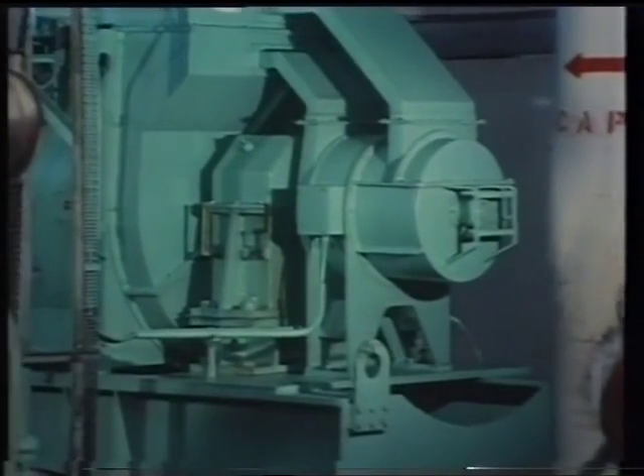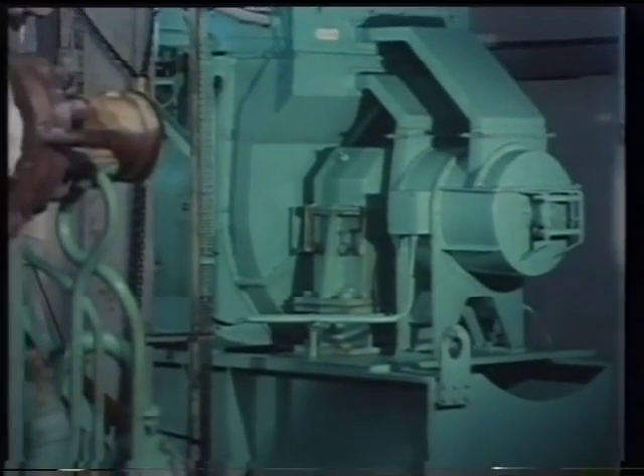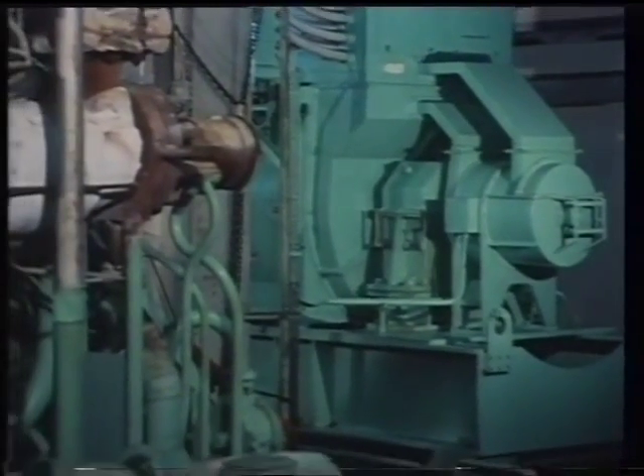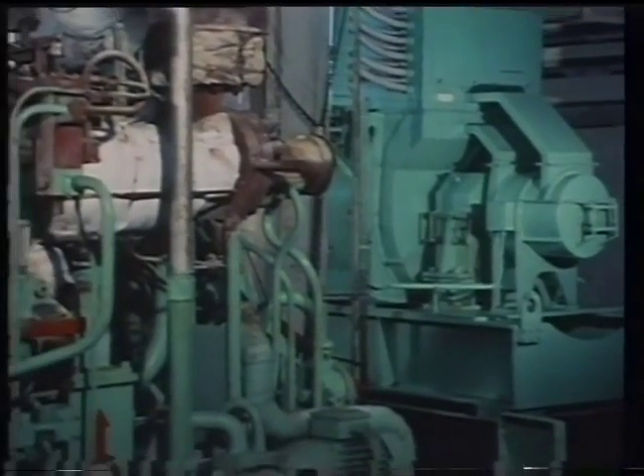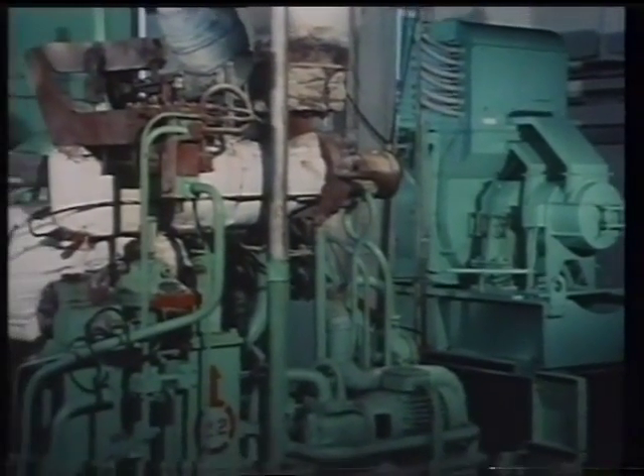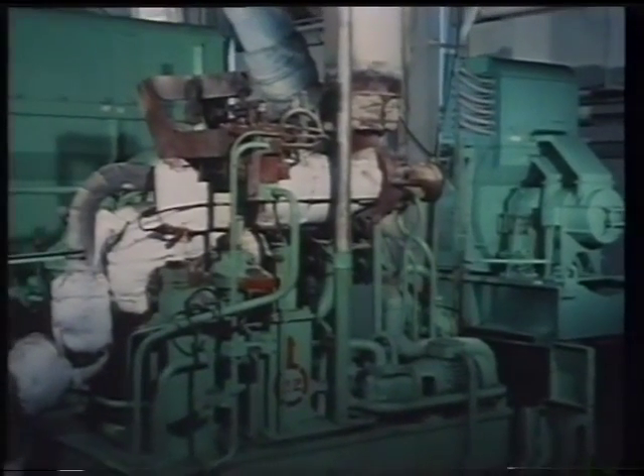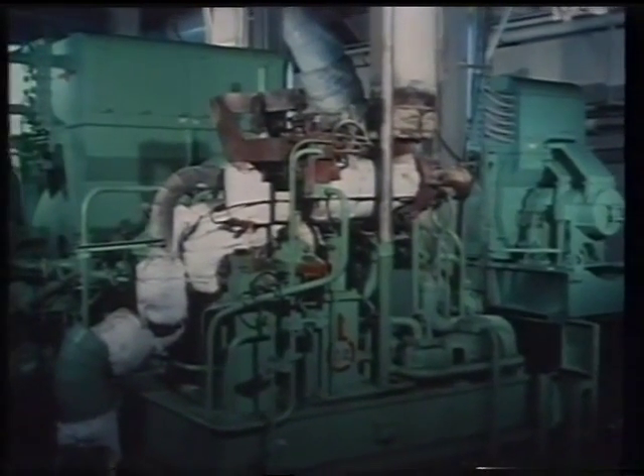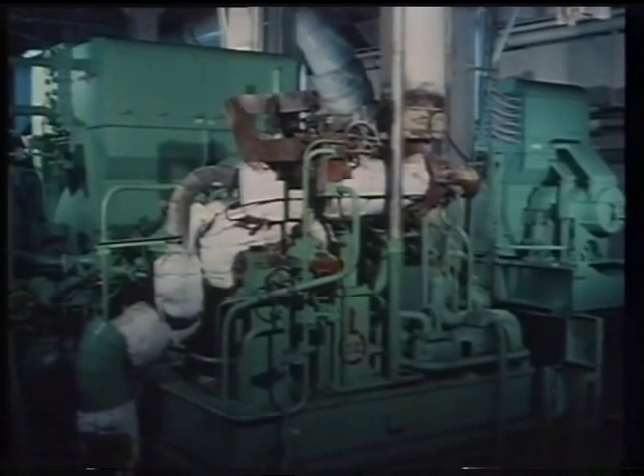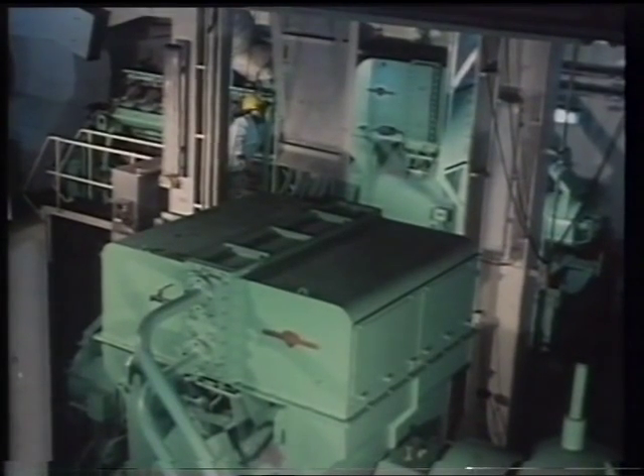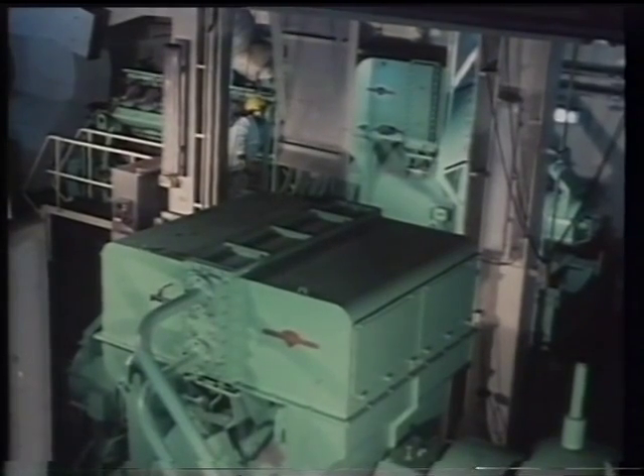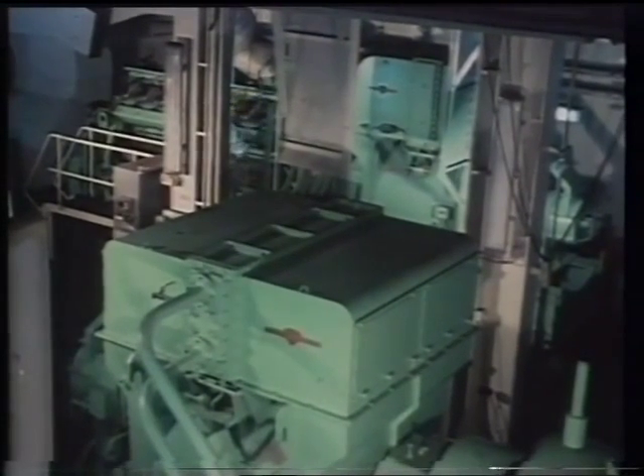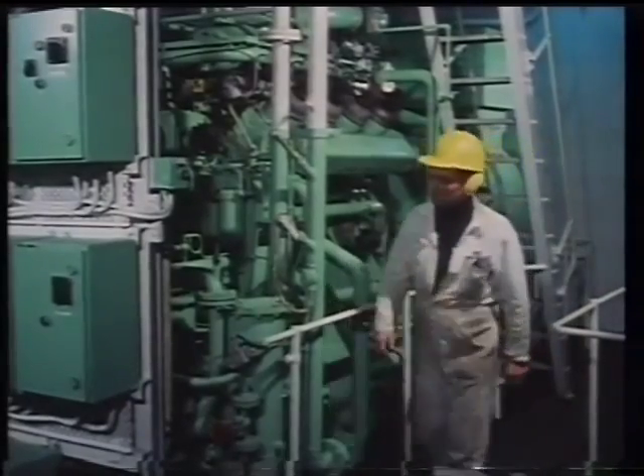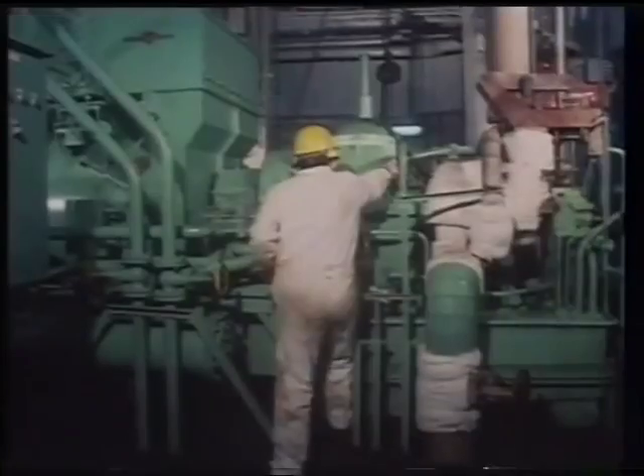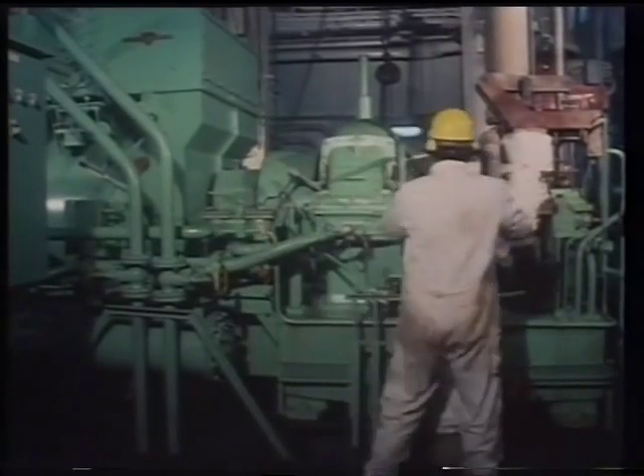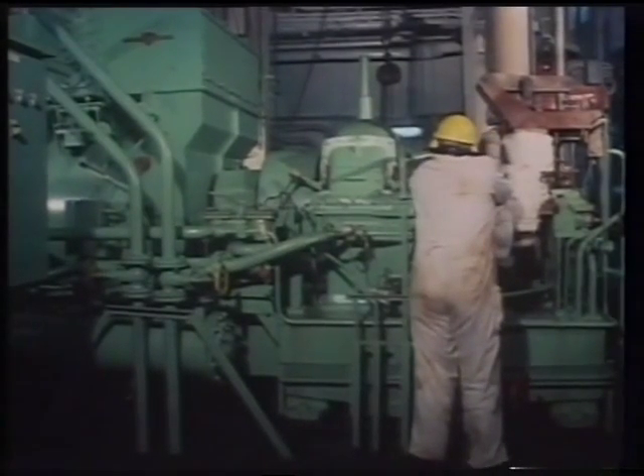A typical scheme of power generation on board ship will have 2 main AC generators, or alternators, and 1 emergency AC generator. But there are many different designs depending on the ship's operating role. The most typical scheme will provide 440-volt 3-phase alternating current at a frequency of 60 Hz. Some ships will have 380-volt 50 Hz systems. There are also high-voltage systems of 3.3 kilovolts and higher in existence, where size and power-to-weight ratio of the equipment is a crucial consideration.